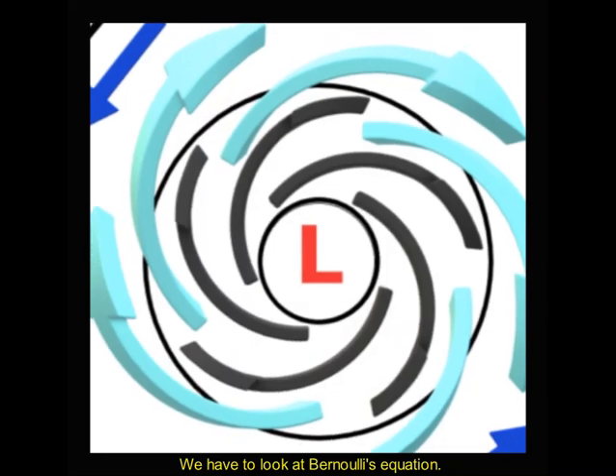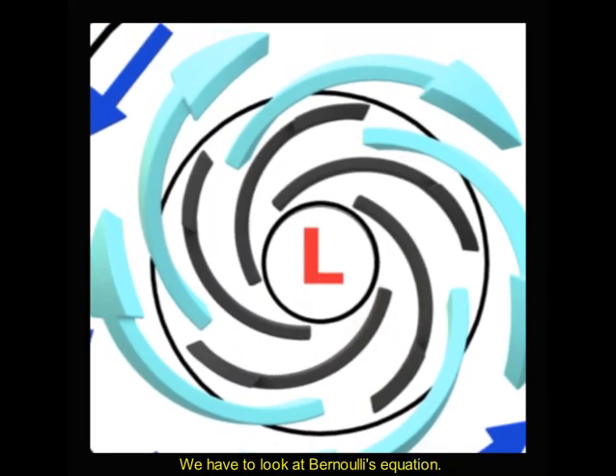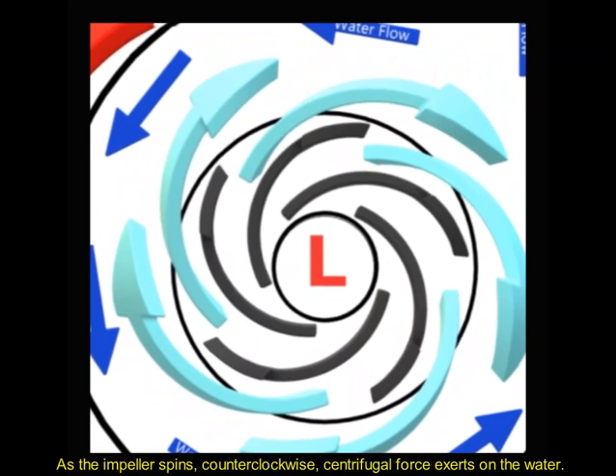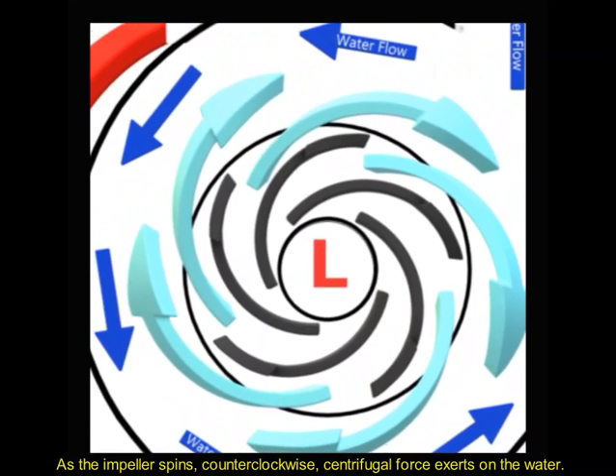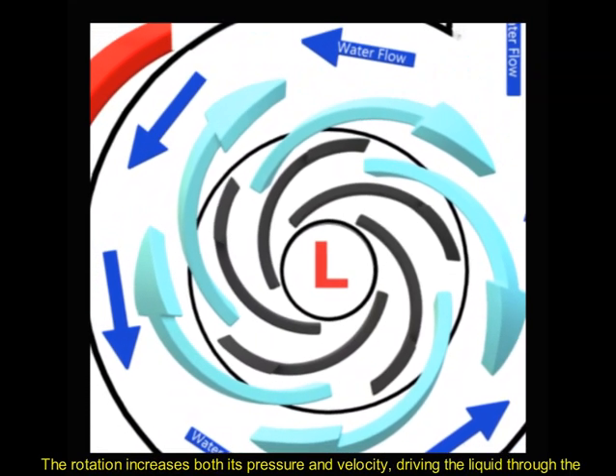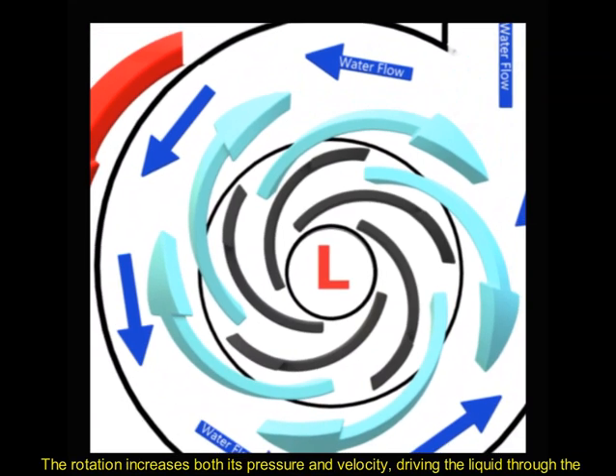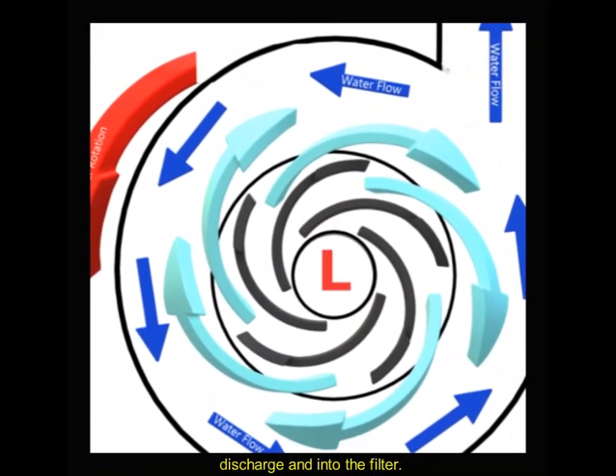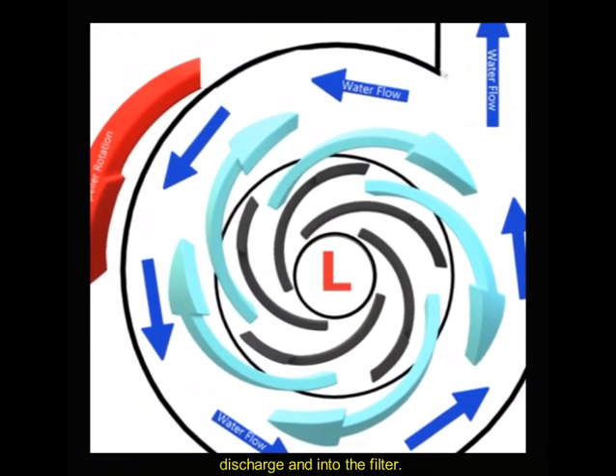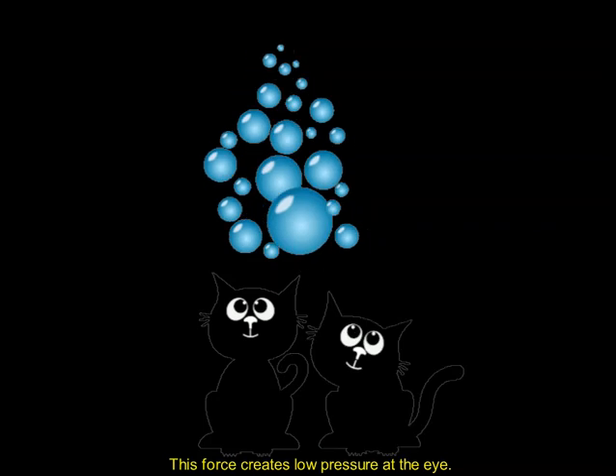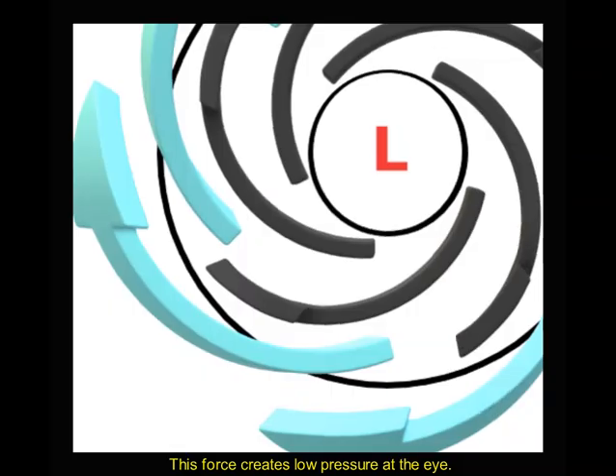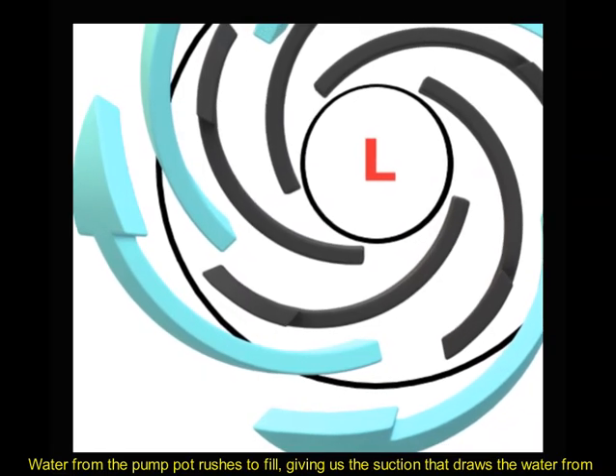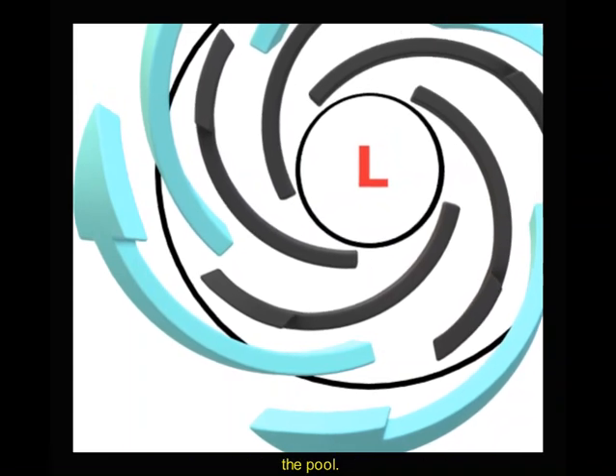We have to look at Bernoulli's equation. As the impeller spins counterclockwise, centrifugal force exerts on the water. The rotation increases both its pressure and velocity, driving the liquid through the discharge and into the filter. This force creates low pressure at the eye. Water from the pump pot rushes to fill, giving us the suction that draws the water from the pool.